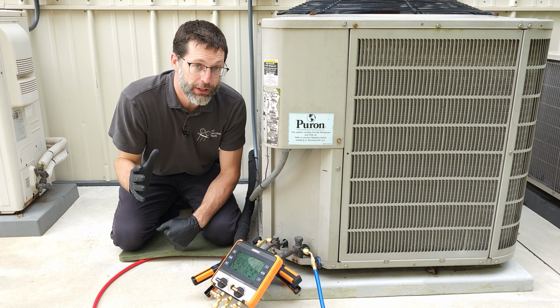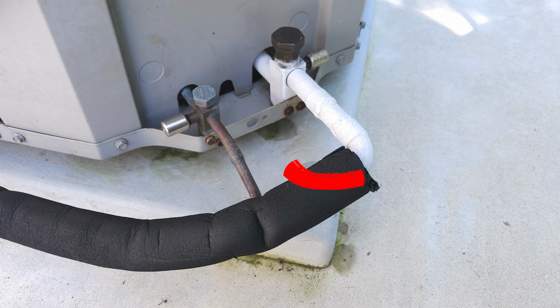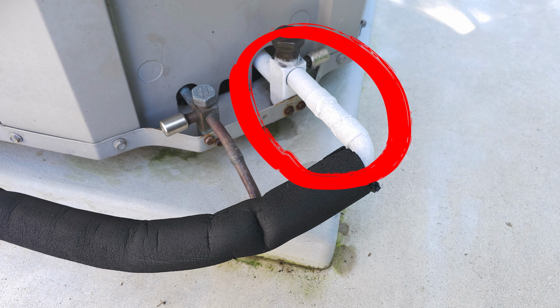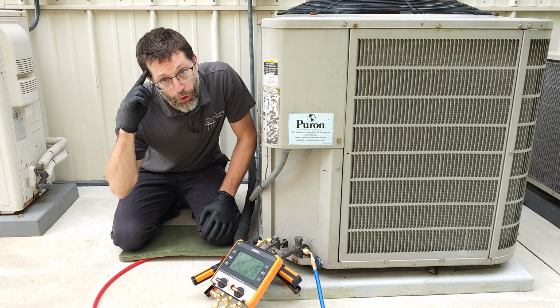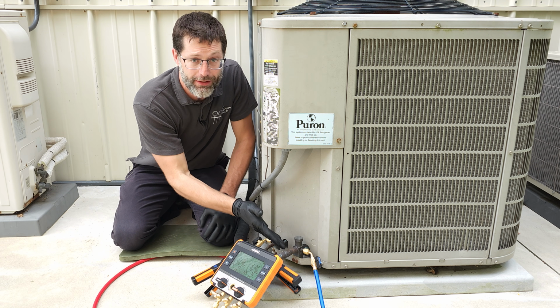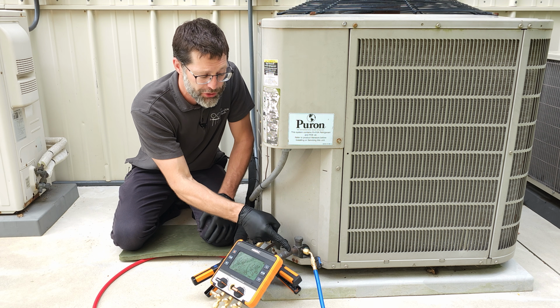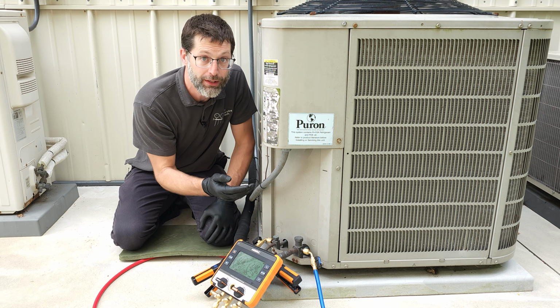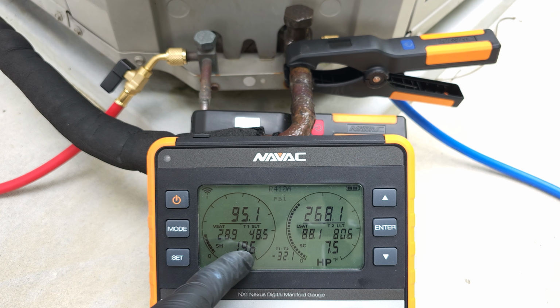In this HVAC training video, we're going over why this suction line is freezing on this outdoor air conditioning unit. It's not what you think, and you don't want to automatically think you're going to add refrigerant into the system in order to raise the pressure and raise the temperature on this suction line. So you've got to take accurate measurements for the whole system.